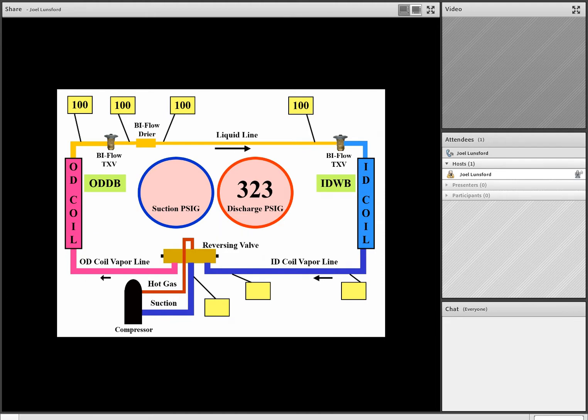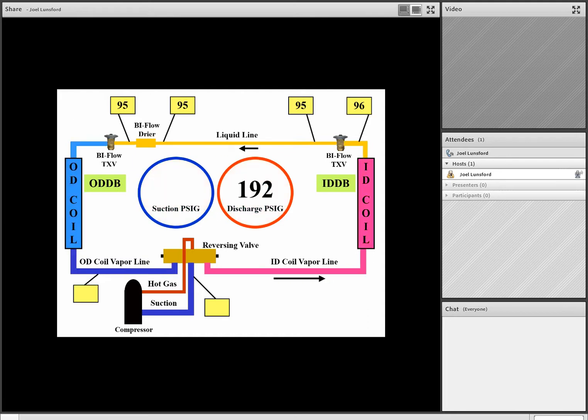In this example, we see we have an R22 service call. We have a white color on the background, and we also notice on our gauges they're not only an R22 call, but we have 192 pounds of pressure on the discharge gauge. Now, team, you'll also notice that we've switched into the heating mode of operation. In other words, the outdoor coil is the cold coil in the heating mode, and the indoor coil is the warm coil in the heating mode of operation. So remember, team, in the heating mode of operation, it's not unusual to see subcooling on the warm indoor coil to be anywhere between about 15 to 25 degrees Fahrenheit. That would be a normal range.